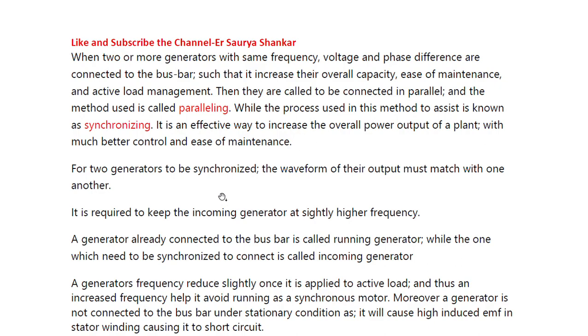For two generators to be synchronized, the waveform of their output must match one another. So the first condition of synchronization is that the waveforms of the two generators have to be the same. It is also required to keep the incoming generator at a slightly higher frequency. This is important — the incoming generator has to be kept at a slightly higher frequency. A generator already connected to the bus bar is called the running generator.